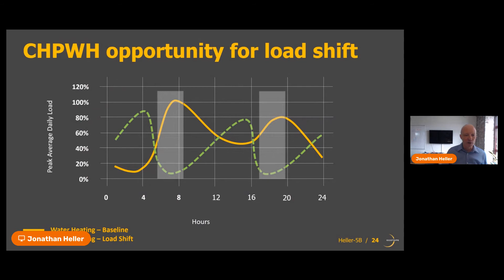The next thing we're going to be working on at the Bayview Tower project is to test, demonstrate, document, and optimize the load shifting capabilities of that system—really trying to shift the operation of the heat pump to low load periods, moving it off the peak hot water demand periods, which typically align with peak utility periods as well. We'll be doing that work this year with funding primarily from Bonneville Power Administration.